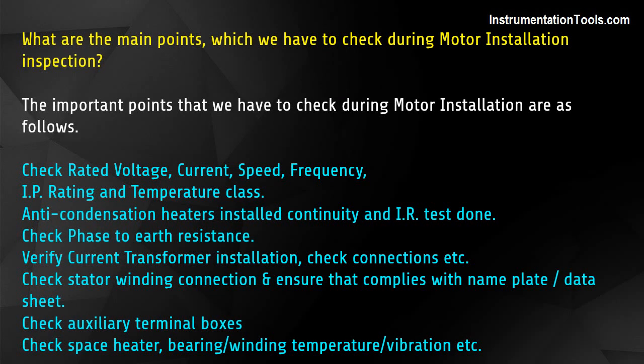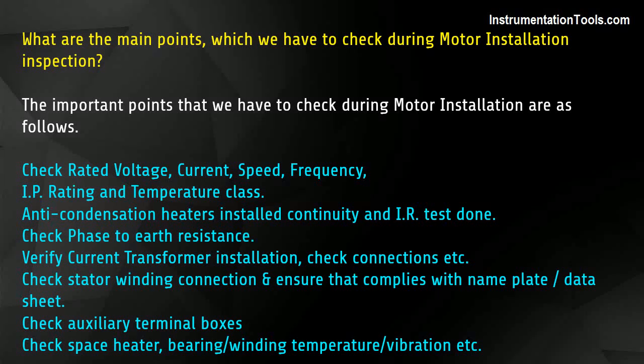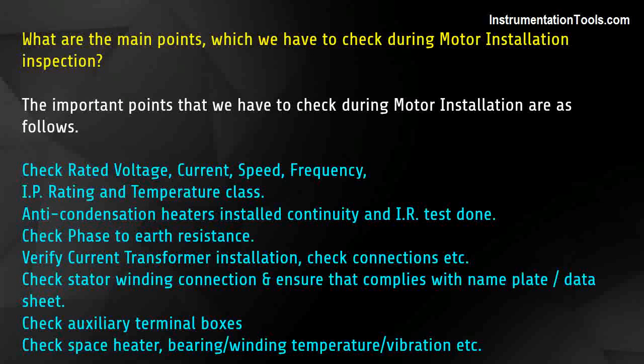Check stator winding connection and ensure it complies with nameplate and data sheet. Check auxiliary terminal boxes, check space heater, and check bearing winding temperature and vibration.